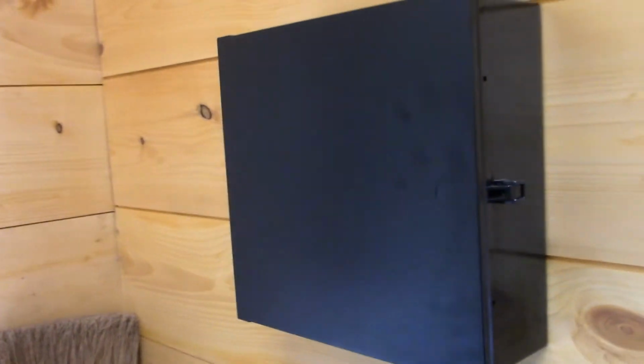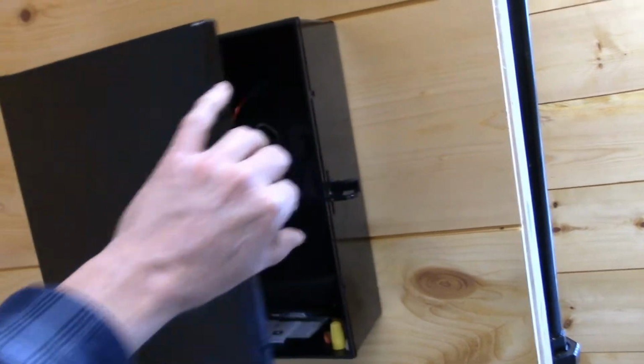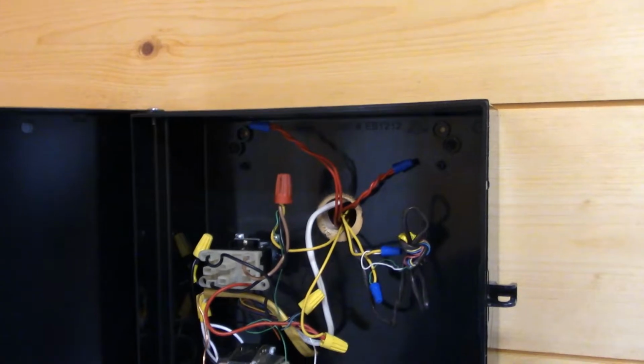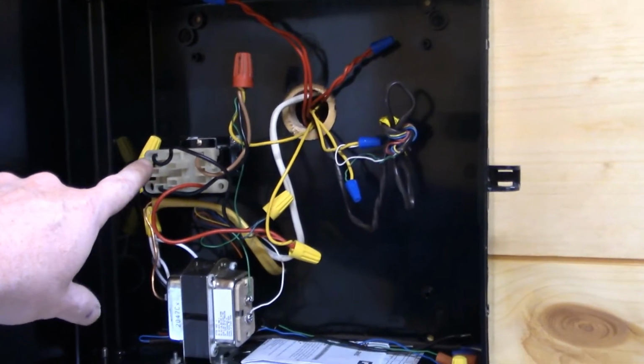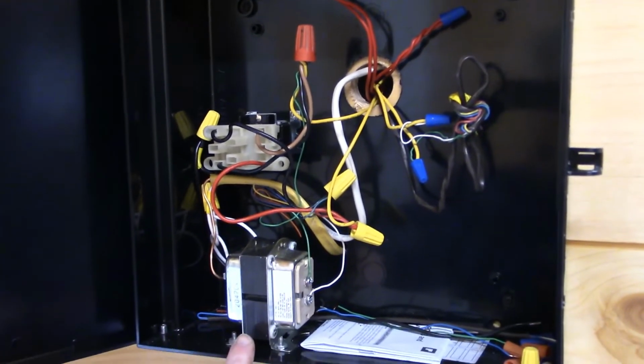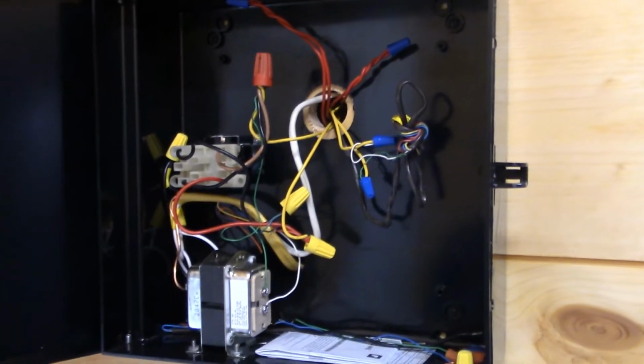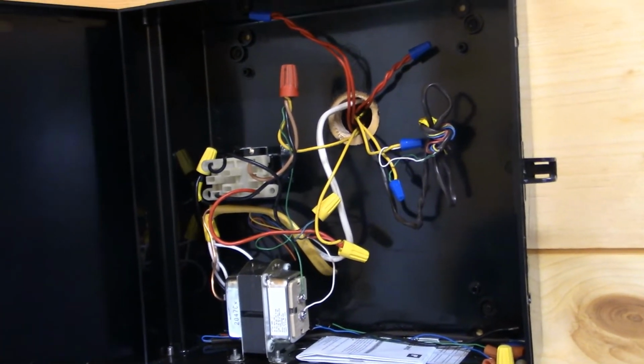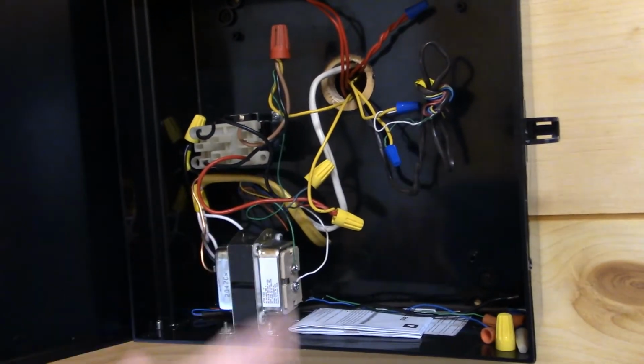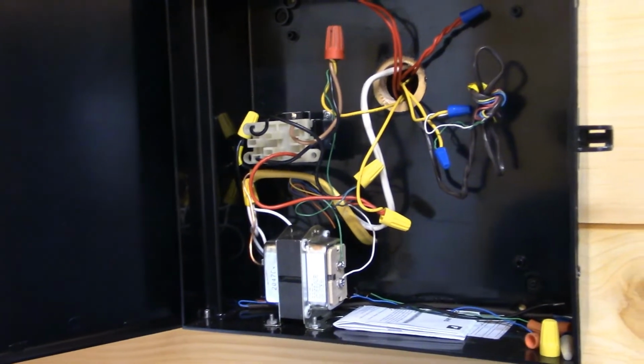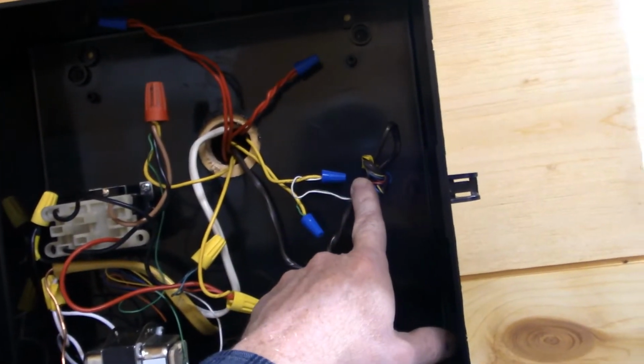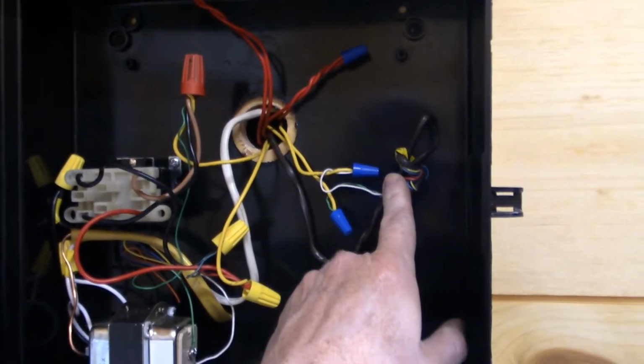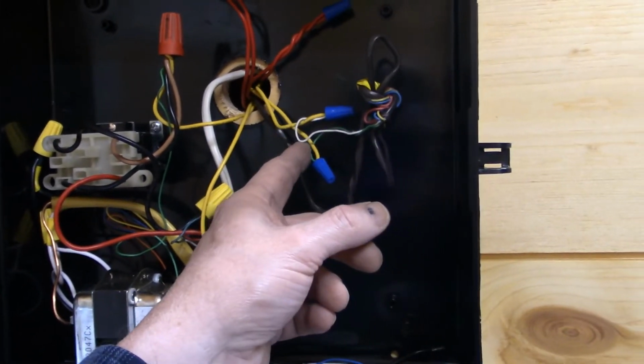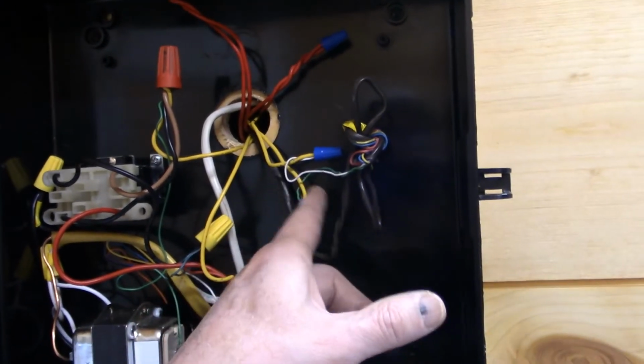Well, right on the other side of this wall here, there's a box. This houses the zone valve controls. It's a little haphazard at the moment, but basically what we have is this relay, which you will hear clunk on and off pretty often, and this transformer control the house heat exchanger zone valve. So whenever the house heat exchanger down in the basement calls for heat, this relay clicks on, turns on the zone valve, and the pump that runs 24/7 just pumps water to it, and that's that. This is the thermostat control for this outbuilding. This goes down into the air handler in the basement, and this just provides 24 volts to the zone valve whenever there's a heat call down there. That's that.